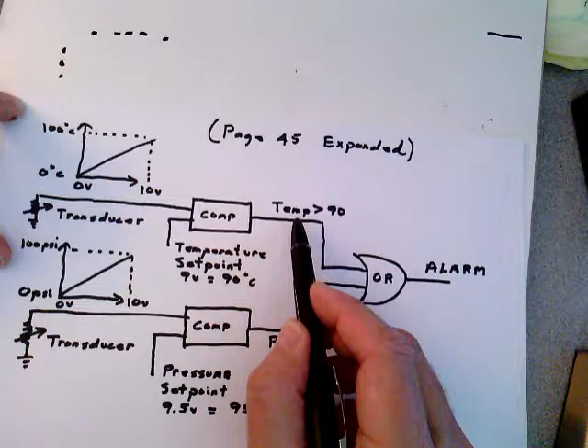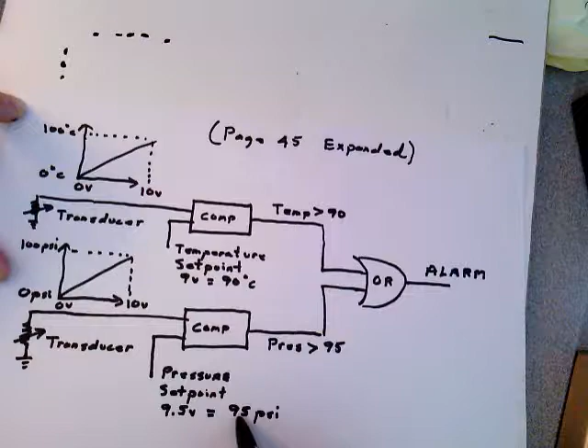Same thing down at this point, except we have a pressure transducer that's linear between 0 volts, 0 psi, and 10 volts, which is 100 psi. So we put a set point down here. In this case, we put 9.5 volts down here that we're comparing the actual measurement to. That's 95 psi. So whenever this voltage on the output of the transducer gets equal to or above 9.5 volts, which would indicate 95 psi, according to our graph here, this will switch to a 1. And when you get a 1 here or a 1 here, you get an alarm.